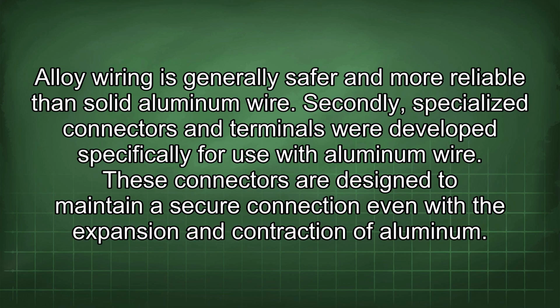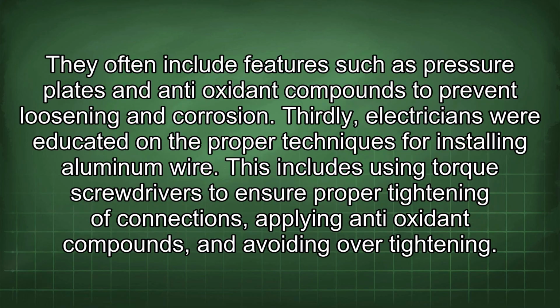Secondly, specialized connectors and terminals were developed specifically for use with aluminum wire. These connectors are designed to maintain a secure connection even with the expansion and contraction of aluminum. They often include features such as pressure plates and antioxidant compounds to prevent loosening and corrosion. Thirdly, electricians were educated on the proper techniques for installing aluminum wire. This includes using torque screwdrivers to ensure proper tightening of connections, applying antioxidant compounds, and avoiding over-tightening.